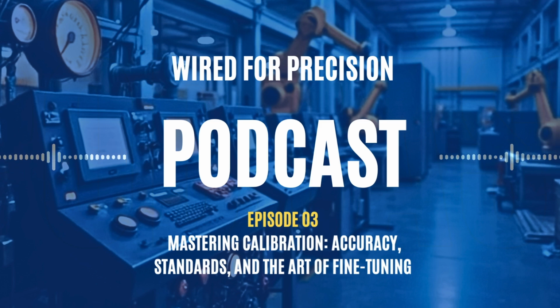Every calibration needs a reference. These are often traceable to national or international standards, like NIST for the US, BIPM for global, or the ISO/IEC 17025 standard for calibration laboratories. Traceability ensures consistency. It means that your instrument's accuracy can be linked back, through an unbroken chain of comparisons, to an internationally recognized standard. For industries under ISO 9001:2015 or regulated environments like GMP, traceability is non-negotiable.